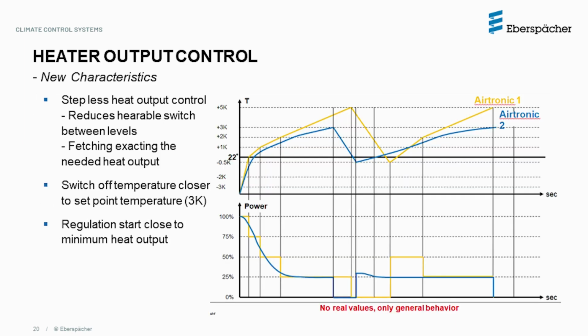When compared, the functional difference between the first generation and the second generation Airtronic heater is clearly visible. These two graphs show the orange line for the first generation Airtronic heater and the blue line for the second generation Airtronic 2 heater. The switch-off temperature is much closer to the set point as compared to the previous generation heater. The first generation Airtronic heater has a delta T of 5 °Kelvin, whereas the second generation Airtronic 2 heater has a lower delta T of 3 °Kelvin. This means that during operation, the second generation Airtronic 2 heater will shut down a whole lot quicker after it reaches the required set point temperature. The graph of the heat output shows that the new second generation Airtronic 2 heater has a smoother curve versus the first generation heater.